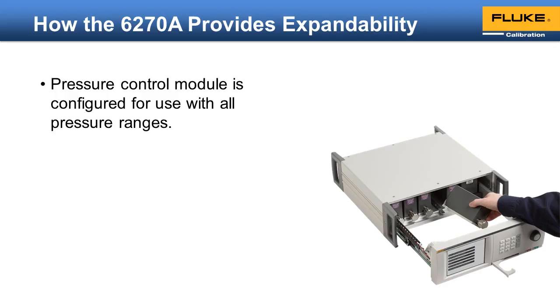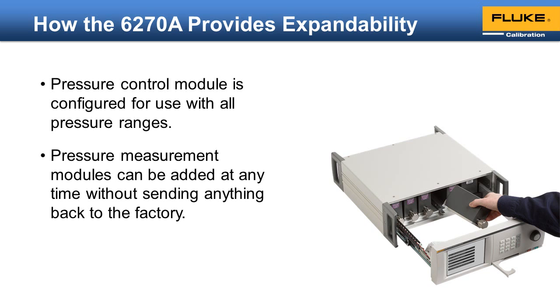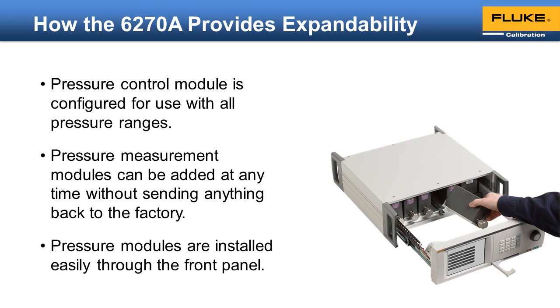This makes it easy to expand the range. Consider a scenario where you purchase a 6270A with just a 100 psi range pressure module. A year later, your requirements expand and you need to cover 3000 psi. When manufactured, the control module was configured to handle 3000 psi, even though it wasn't originally required to. So now, you can add a 3000 psi module without sending the instrument back to the factory. The pressure modules are easily installed through the front panel, and the 5 available slots make it easy to expand.